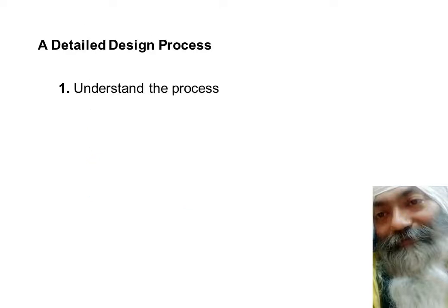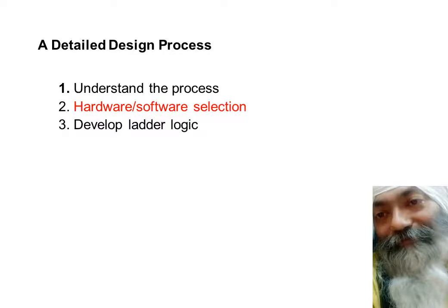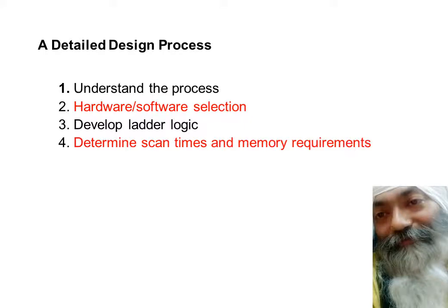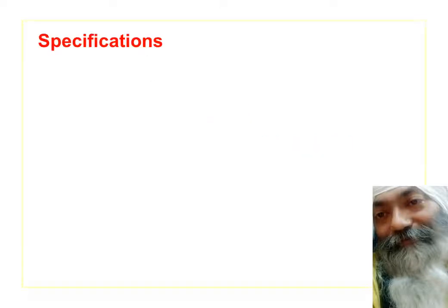We have to have a detailed design process, and before selecting the PLC, we just cannot randomly go in for any PLC. First of all, we have to understand the process. We have to understand the hardware and software selection of the process. We have to develop ladder logic for that, and after having developed ladder logic, we have to determine the scan times and the memory requirements. Only then we can say, okay, this is the kind of PLC I want to purchase.